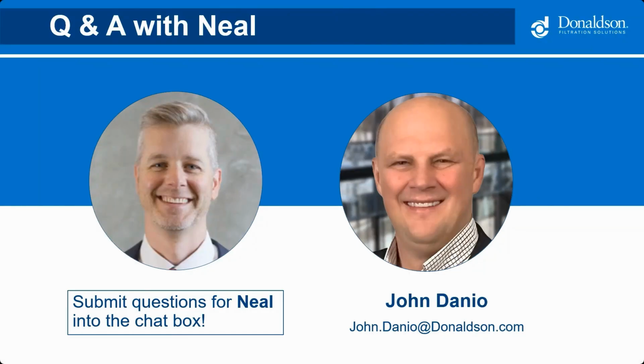So this is the same person asking that. So when running a DHA, say when they conduct a DHA, do you design for normal operation or do you design for upset operations, spilled bags, equipment failure, et cetera, or both? It's a combination of both. And really that comes down to risk. So when you have a DHA done by an outside company, they are looking at normal operating procedures, and then they're trying to identify potential upsets and risks that can happen and put mitigation strategies in place so that if those happen, everybody's safe. Thank you.